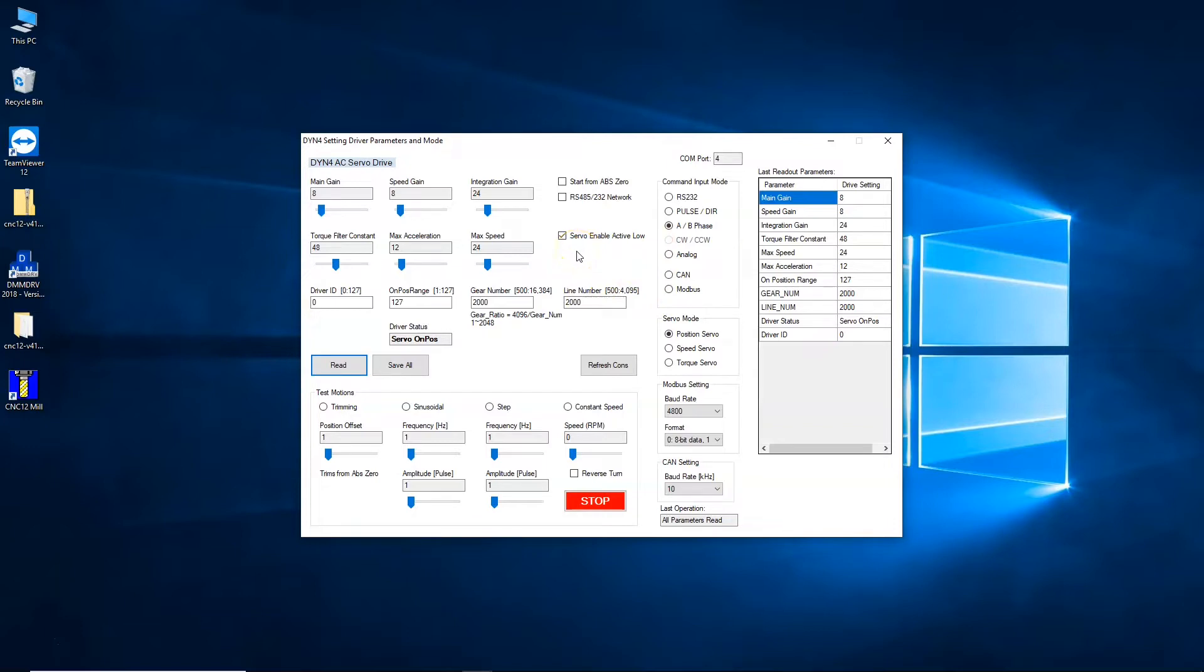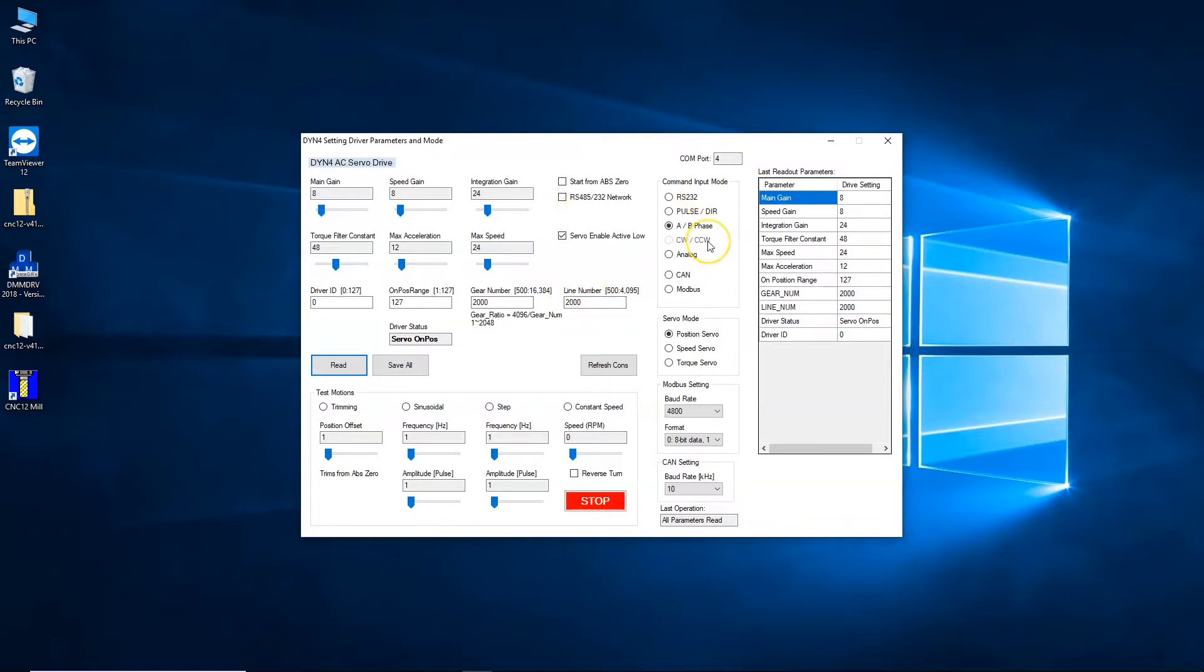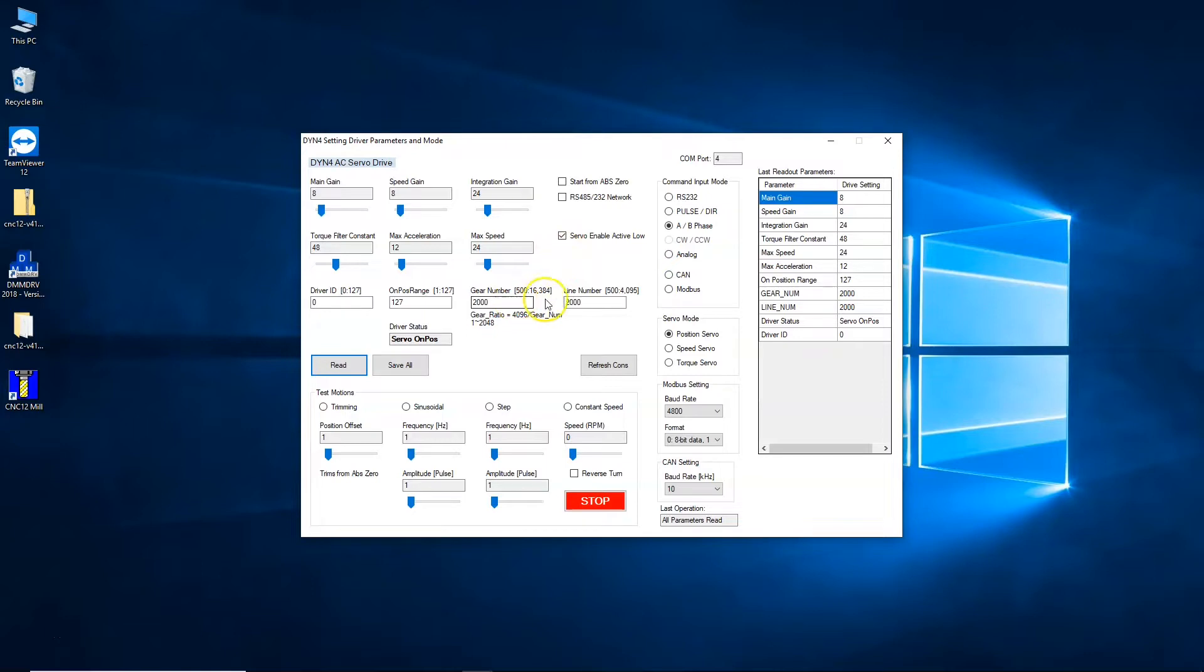Set the gear number and the line number. I have gear number set to 2000 and line number set to 2000. We set the servo drive into AB phase command input mode, we set servo mode into position servo, we set enable active low, and we set gear number and line number to 2000. Now we just save these parameters.